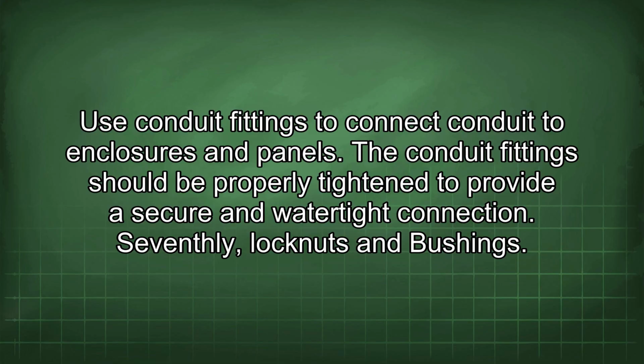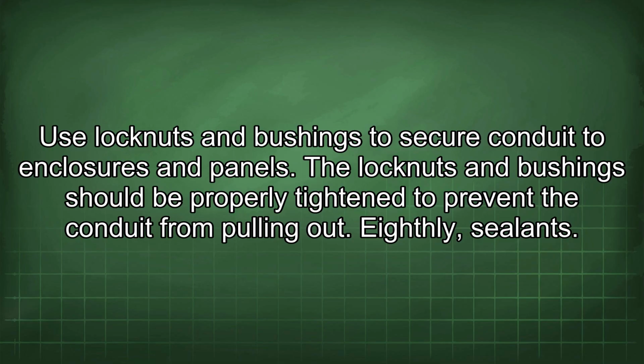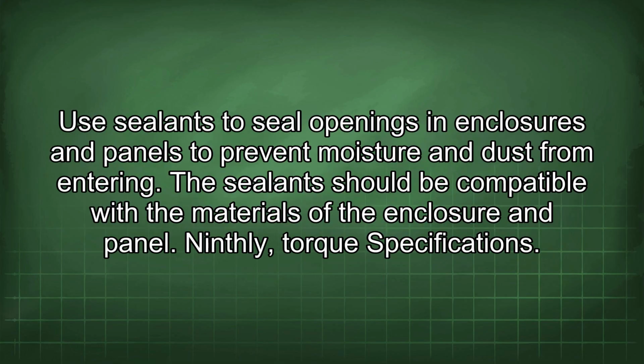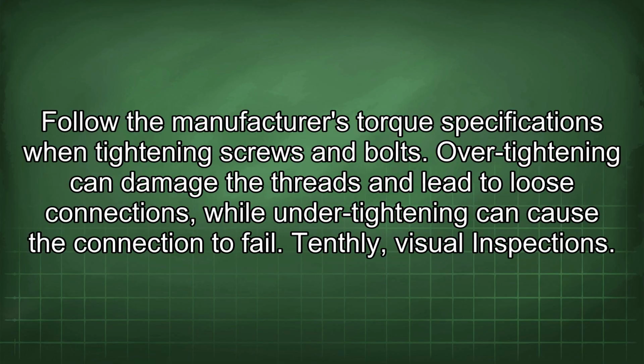Seventhly, lock nuts and bushings. Use lock nuts and bushings to secure conduit to enclosures and panels. The lock nuts and bushings should be properly tightened to prevent the conduit from pulling out. Eighthly, sealants. Use sealants to seal openings in enclosures and panels to prevent moisture and dust from entering. The sealant should be compatible with the materials of the enclosure and panel. Ninthly, torque specifications. Follow the manufacturer's torque specifications when tightening screws and bolts. Over-tightening can damage the threads and lead to loose connections, while under-tightening can cause the connection to fail.